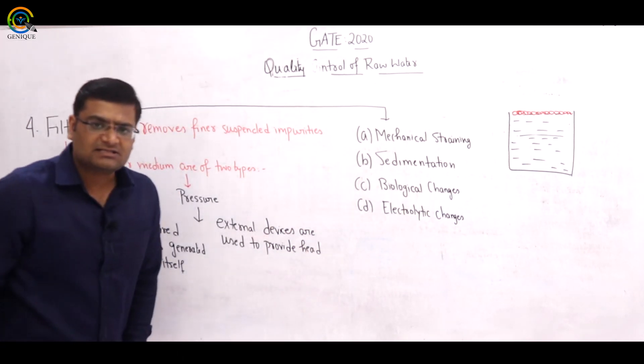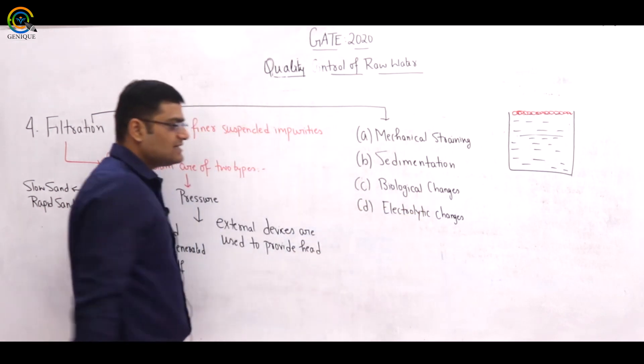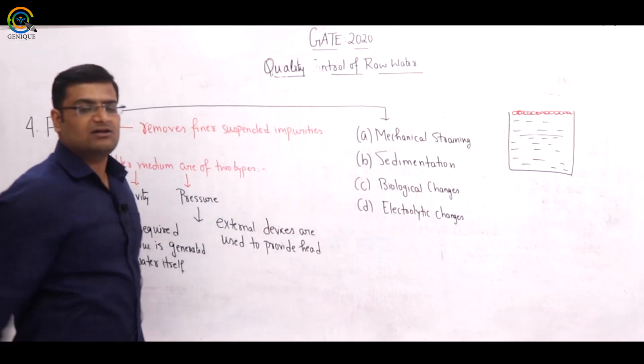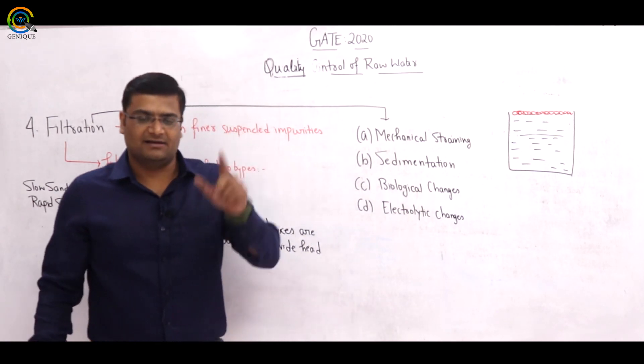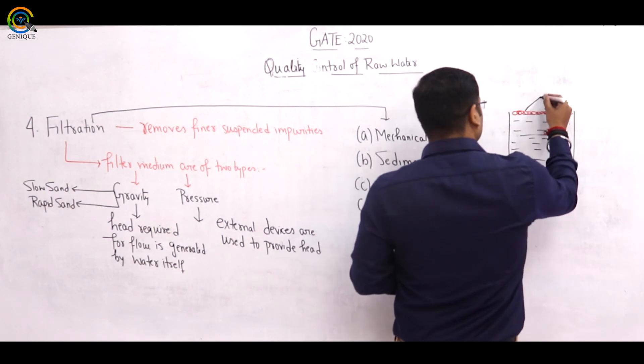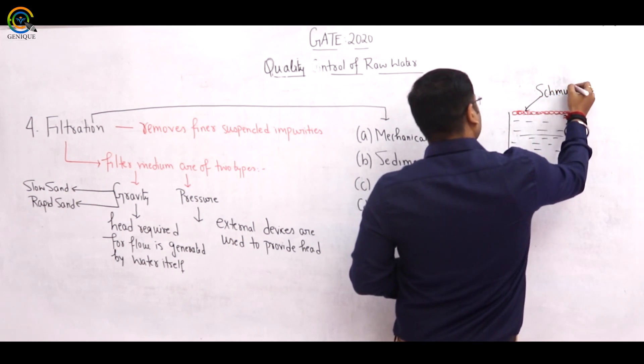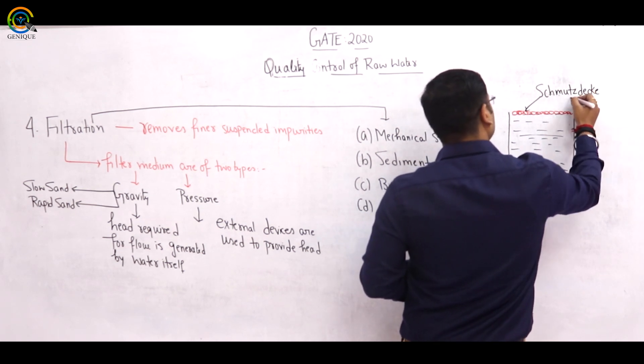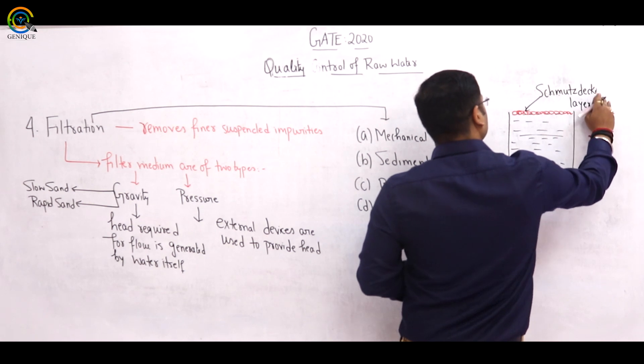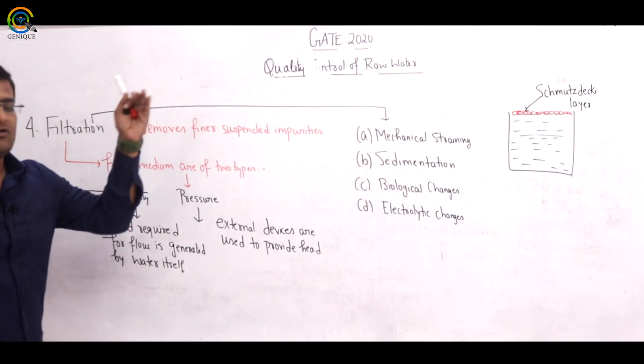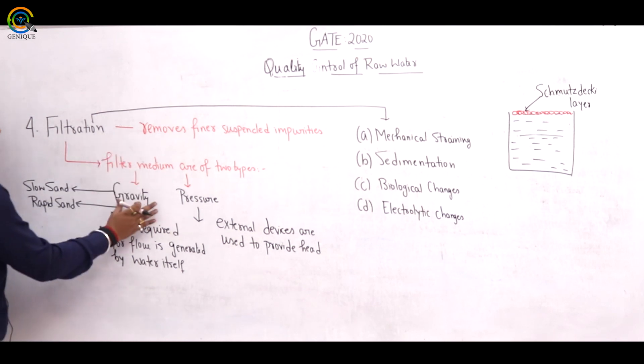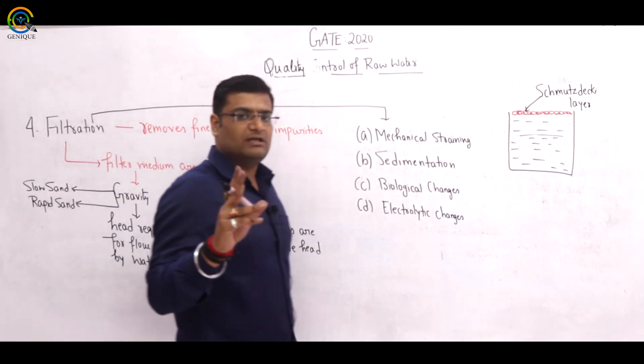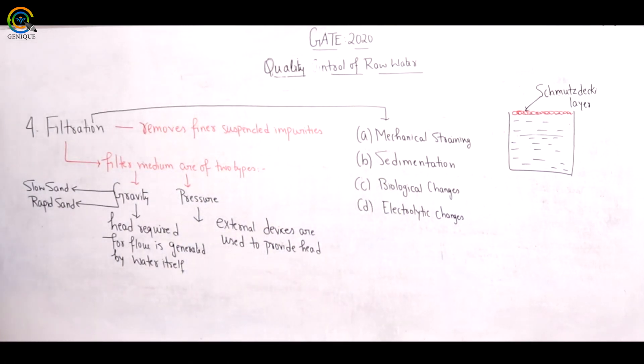So these four steps — mechanical straining, sedimentation, biological changes, and electrolytic changes — constitute the filtration process. The top layer where biological changes occur is called the schmutzdecke layer. Filter media are of two types: gravity filter (with slow sand and rapid sand sub-types) and pressure filter.